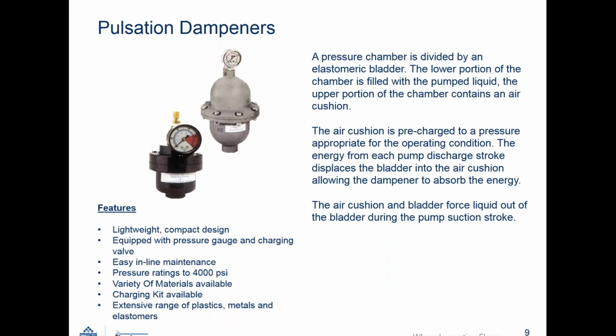Pulsation dampeners. Dampeners are generally used with positive displacement pumps. The stroking of the pump causes an energy going through the piping that can cause vibration. Generally, when you want to eliminate these pulsations and the vibration from your piping, dampeners are used. The dampeners are generally installed right at the exit of the pump, and it stops up to 95% of that pump's pulsation. It basically has a bladder on the upside of the unit, and the unit is charged from the top portion, and when the energy comes through the bottom, it absorbs that pulsation coming into the dampener.